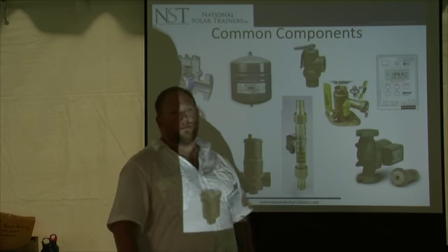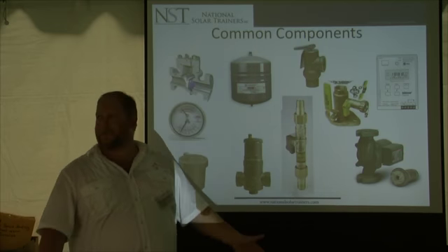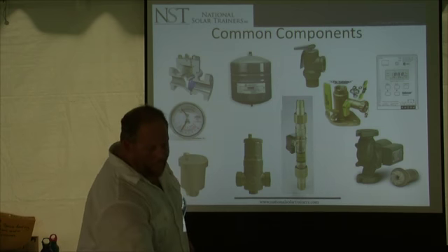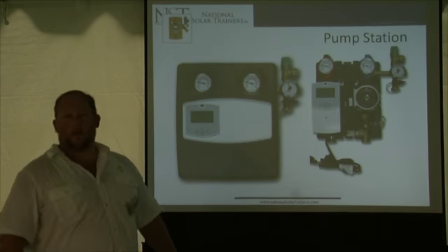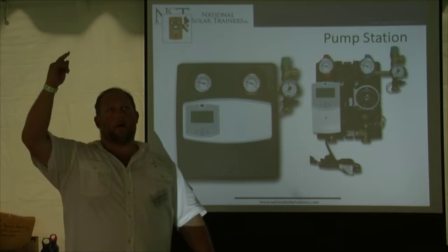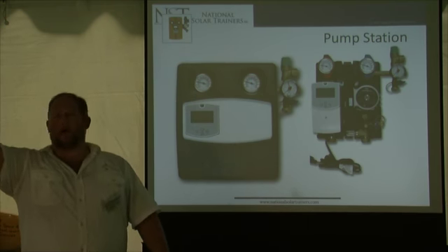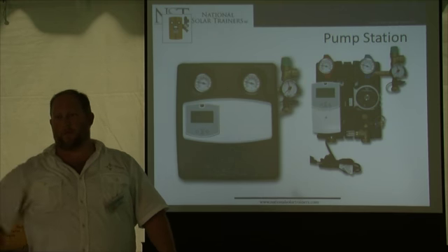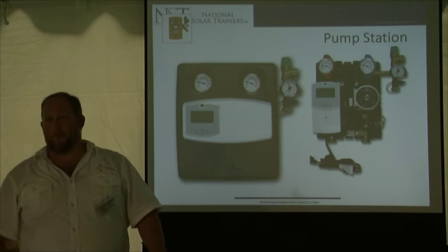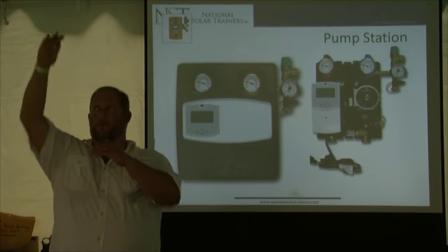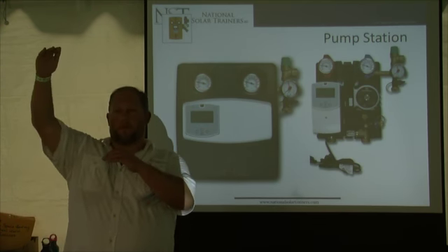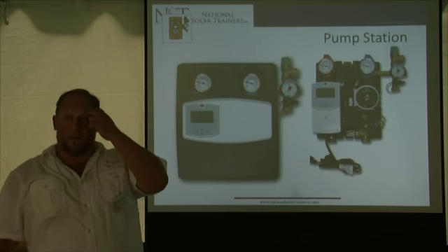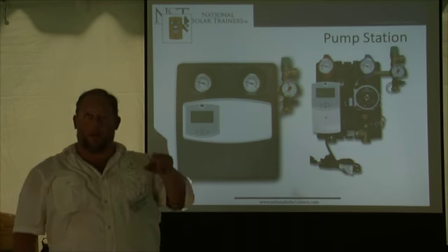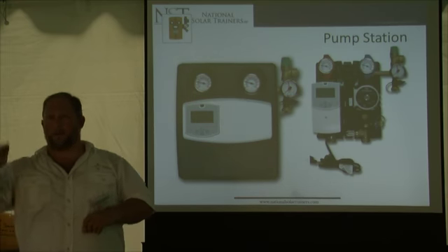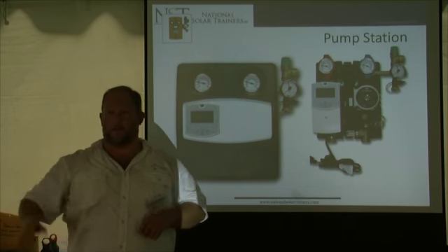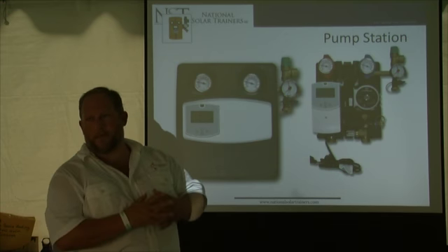Obviously, the pressure relief valve: it's a closed loop. All closed loops need a pressure relief valve. Where do you want to see the expansion tank? I want to see it downstream or above the pump. In front of the pump, between the pump and the collectors. Okay, so on the way back to the cool side. On the way back to the collectors, correct. Between the pump and the collectors on the cool side. I'll show you a diagram that has that.